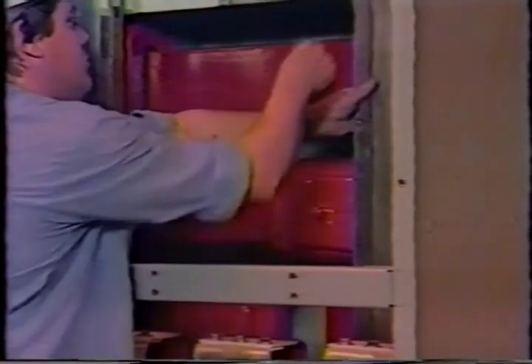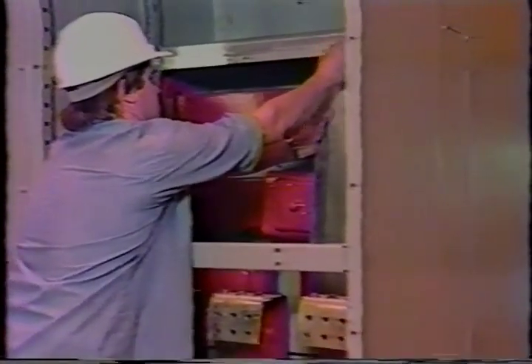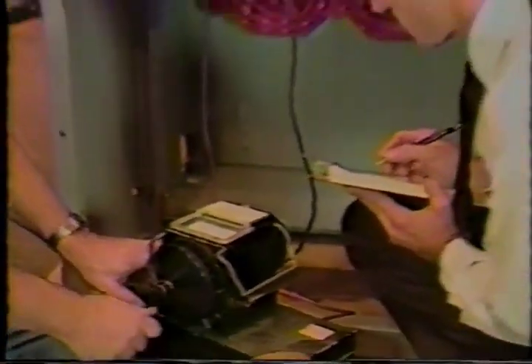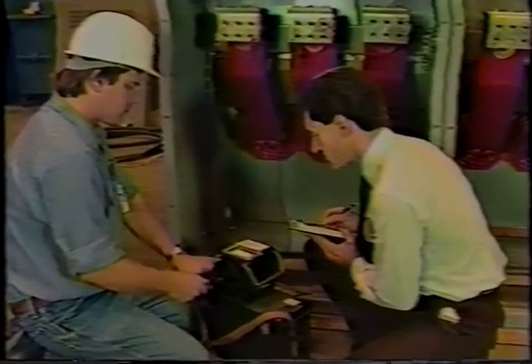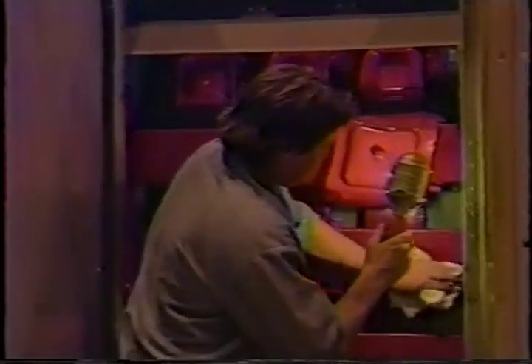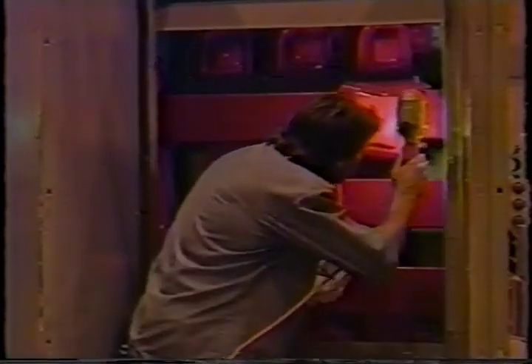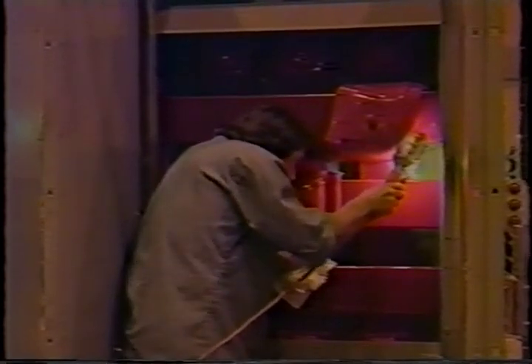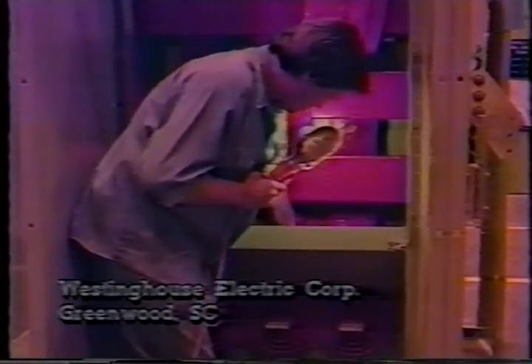For maintenance of buses and connections, de-energize primary circuits and remove cover plates from the primary compartments. Before cleaning, take megger readings between phases and to ground. Inspect for signs of overheating or weakened insulation. Remove dust from buses, connections, supports, and enclosure surfaces. A vacuum cleaner with a long nozzle will be helpful. Wipe clean with a warm soap water solution. Wipe dry.